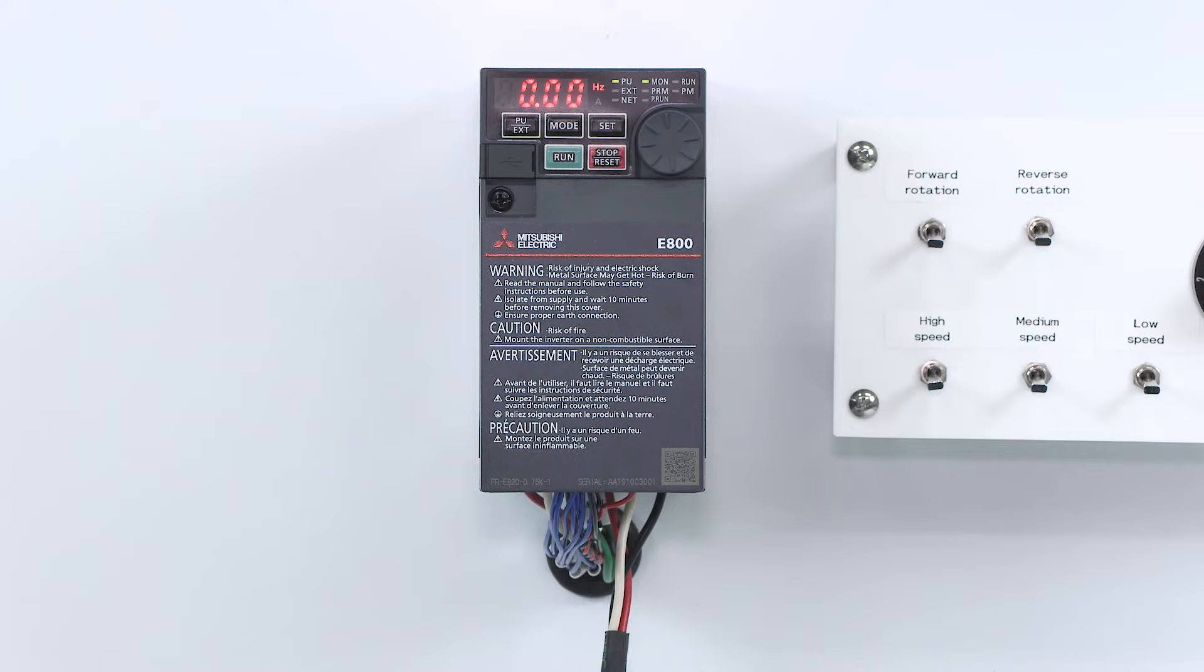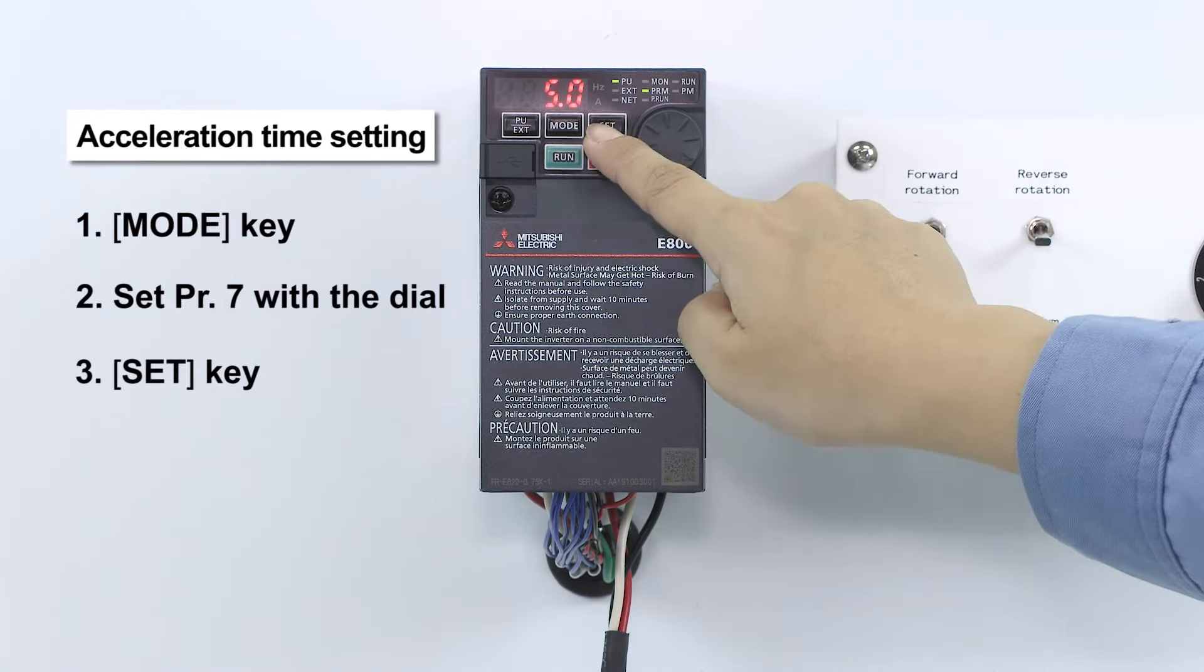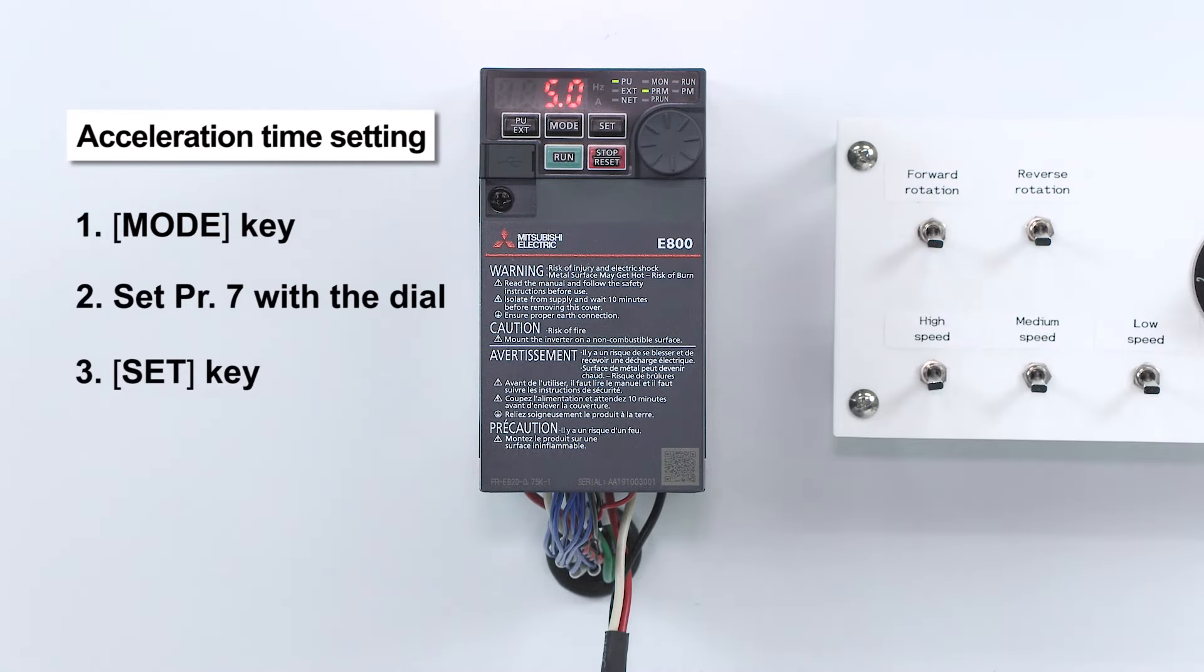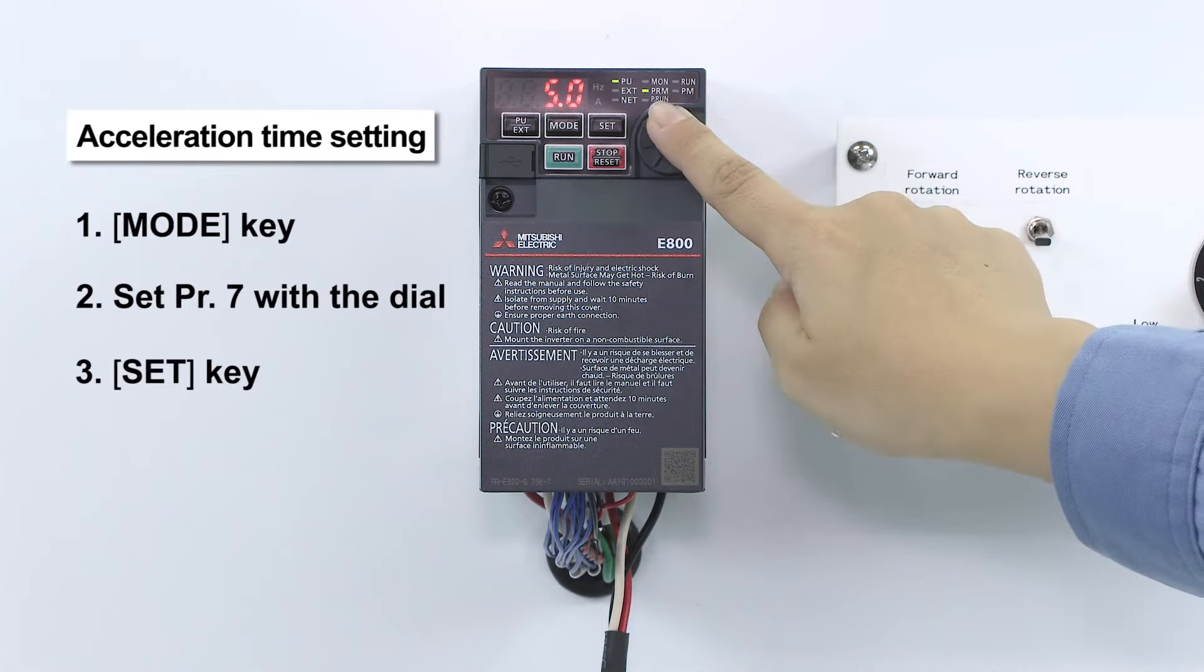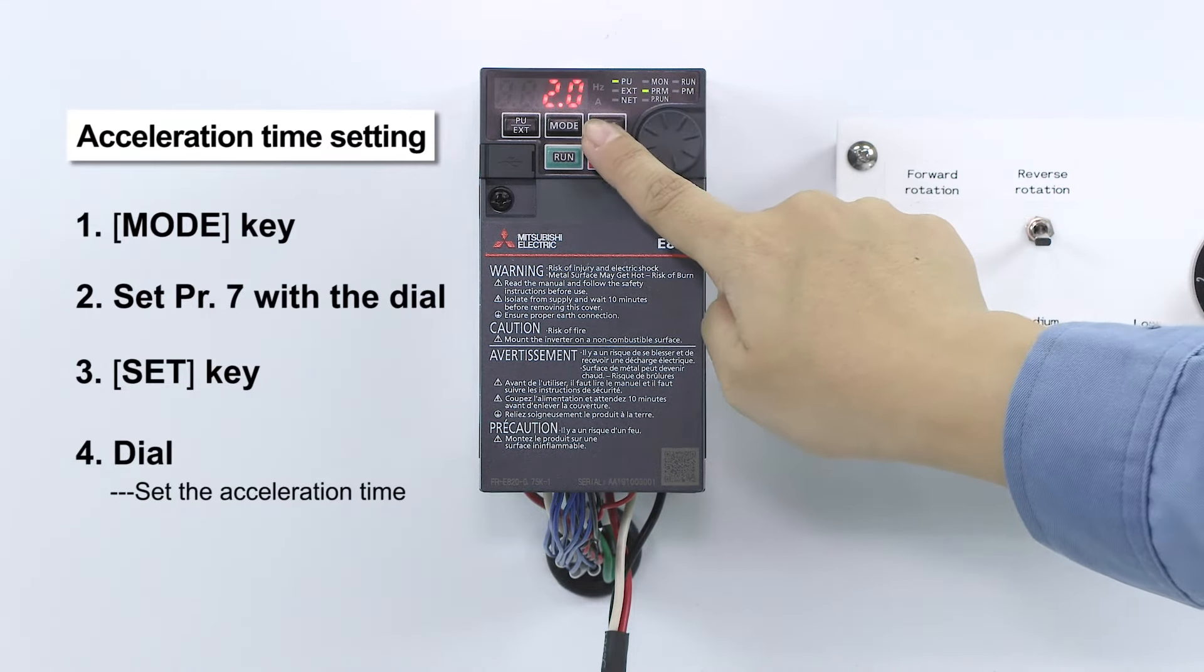To set parameter 7, push the MODE key. Select parameter setting mode and turn the dial to 7. Parameter 7 controls the acceleration time from when the motor starts until it reaches the selected frequency.